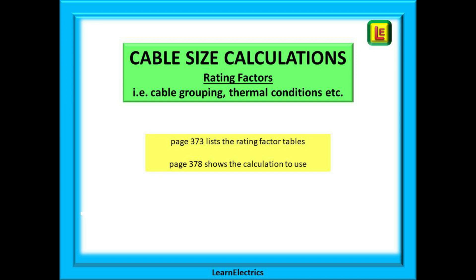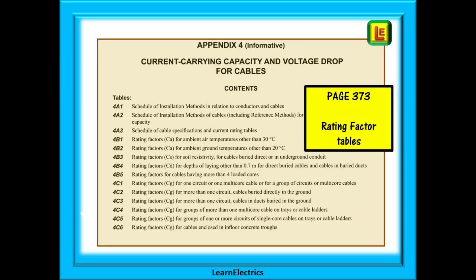We want the cable to be big enough to carry the full load current safely but not so big that it costs us or the customer too much money for extra copper. On page 373 we can see a list of tables that list data for all the conditions that might affect our cable. These are known as rating factor tables. Get to know them. It matters in the exam.